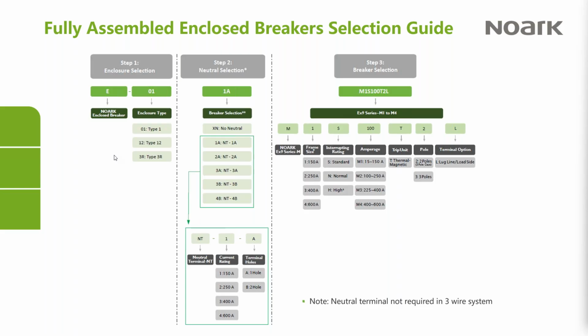The M3, our 400 amp breaker, is available with 2 different configurations of the lugs on the breaker. There's a single hole connector for a larger cable, and a 2-conductor connector for using parallel runs of a smaller conductor. So we give you the option of choosing a neutral that suits that particular breaker frame. Okay, so that's how you select the neutral. And then moving on, the next step is selecting the specific breaker. So it's the M series breaker, frame 1, 2, 3, or 4, depending on the amp range.